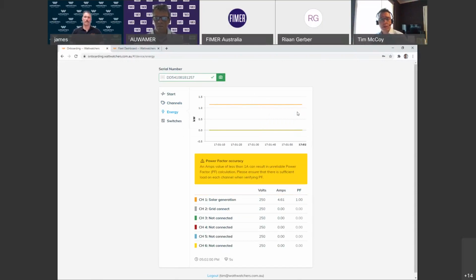So as an installer in the field with this on your phone, you can not only check that the CTs are installed the right way and that the data is coming through cleanly, but now we're going to show you how you actually test the disconnect in the field, which is another part of the South Australian requirements process.